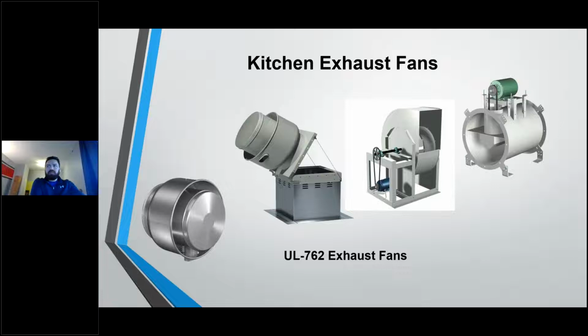The most commonly seen exhaust fan in a kitchen ventilation system would be your upblast exhaust fan. So things to keep in mind when designing an upblast exhaust fan. The wind band of this, so they always need to have a hinged curb cap. Reason for this is a guy has to be able to lift up that curb cap and go from the top and clean the grease duct from the top of the roof. Then the wind band, so obviously this curb cap is shown to be tilted up, but the wind band of the upblast exhaust fan has to be at least 40 inches above the finished roof deck.